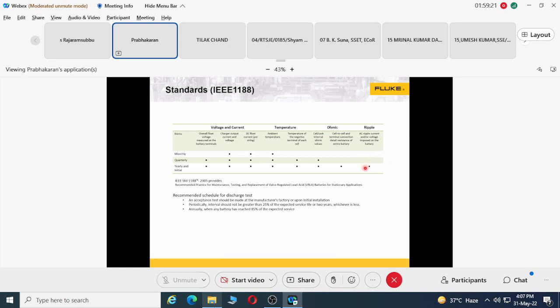Over a year, there are other tests: charger output voltage and current monthly testing is required, DC float current is recommended monthly, and ambient temperature is recommended monthly. There are also quarterly measurements like overall float voltage, charger current and voltage, DC float current and ambient temperature, then temperature of the negative pole and cell resistance.